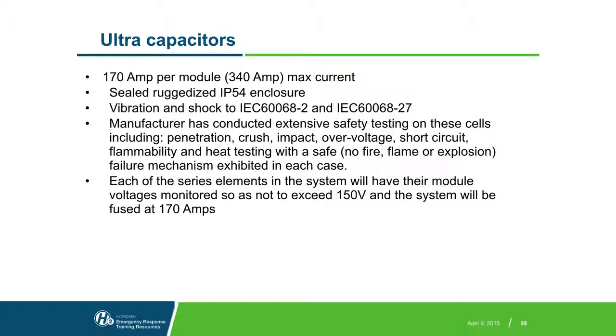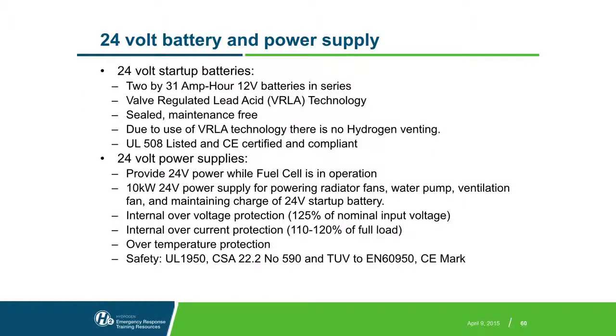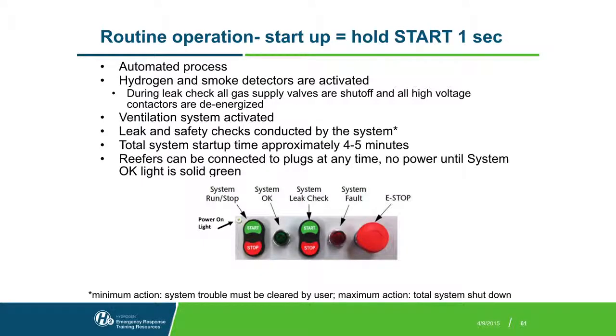The lines themselves have been dissipated. There's a 24-volt battery, the startup batteries, which also powers the sensors in that leak check mode, along with the power supply. Just some specs on those. For routine operation, the reefers can be connected to those 10 plugs at any time, but it's not until this green system light is okay and solid green that those reefers will be powered.